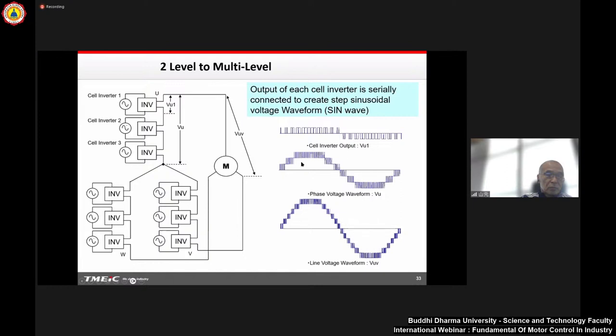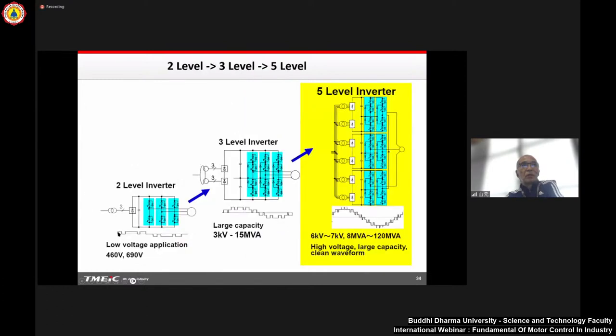How we change two level, three level, and five level: two level can only output plus and minus. The three level actually has each phase with two DC buses - one positive bus and one negative bus. Each phase can output positive voltage and negative voltage, combined with phase-to-phase voltage becoming the three-level voltage as shown here.